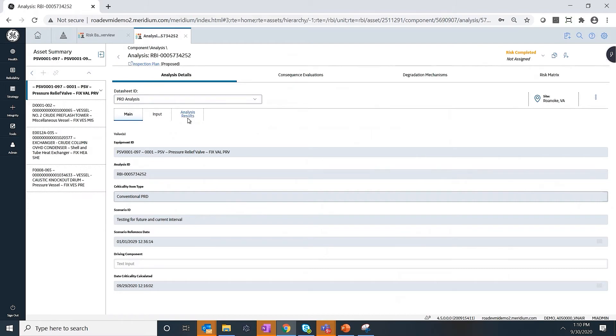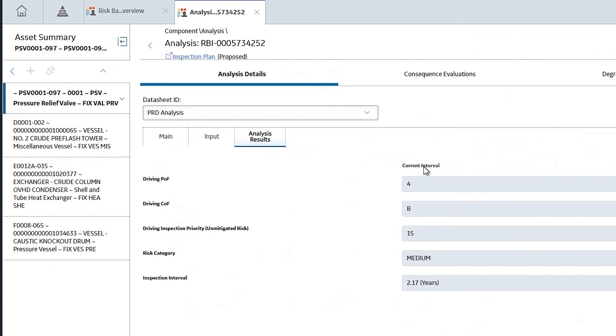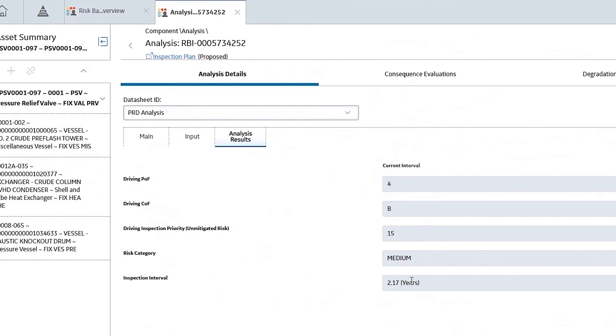If I get into this analysis, what it tells you from the analysis result is what is your driving probability of failure based on your current interval — which means if you are doing a time-based inspection at an interval of 2.5 years or two years, this is your current risk. The risk category is medium, and your current inspection interval is, say, every 2.5 years or two years. But the RBI module tells you if you extend your interval by five years, your risk category is going to jump by one level, which is medium to medium-high.